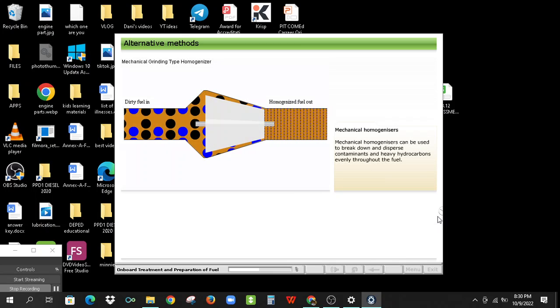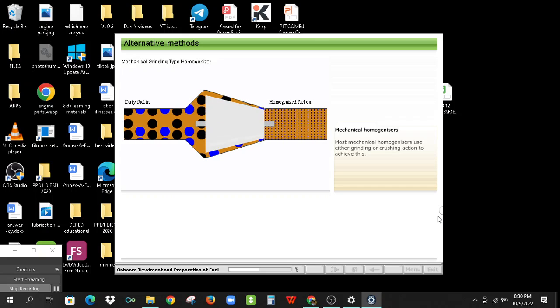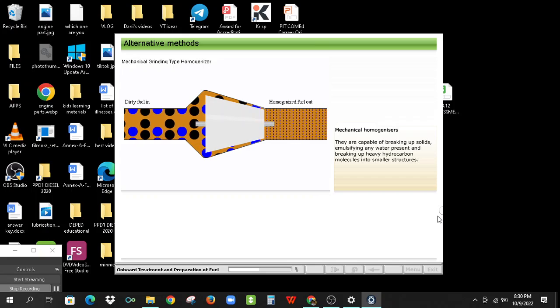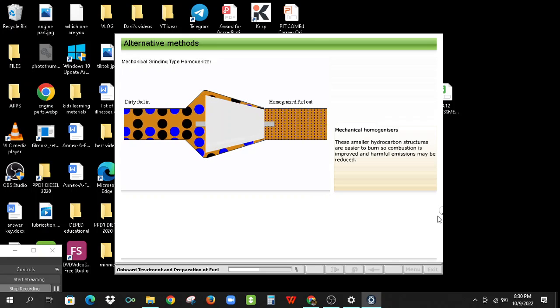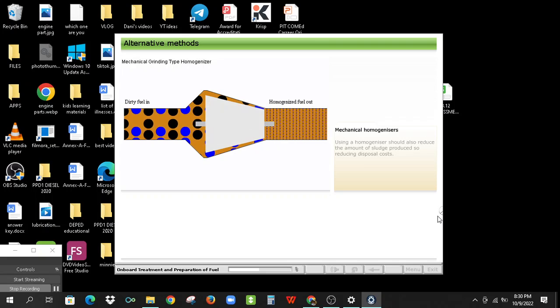Mechanical homogenizers can be used to break down and disperse contaminants and heavy hydrocarbons evenly throughout the fuel. Most mechanical homogenizers use either grinding or crushing action to achieve this. They are capable of breaking up solids, emulsifying any water present, and breaking up heavy hydrocarbon molecules into smaller structures. These smaller hydrocarbon structures are easier to burn, so combustion is improved and harmful emissions may be reduced. Using a homogenizer should also reduce the amount of sludge produced, so reducing disposal costs.